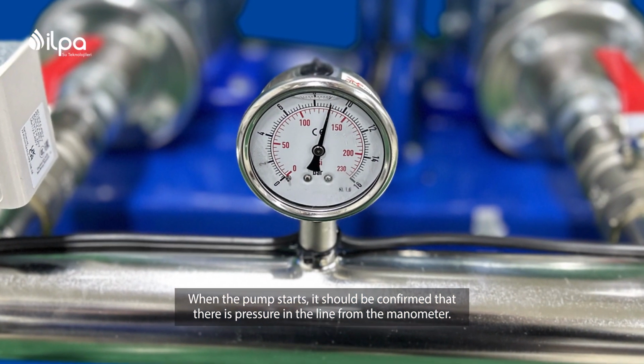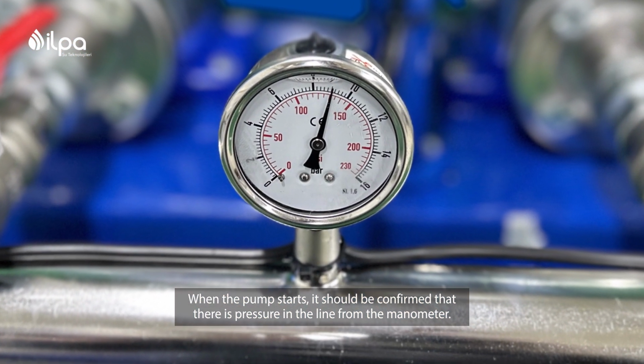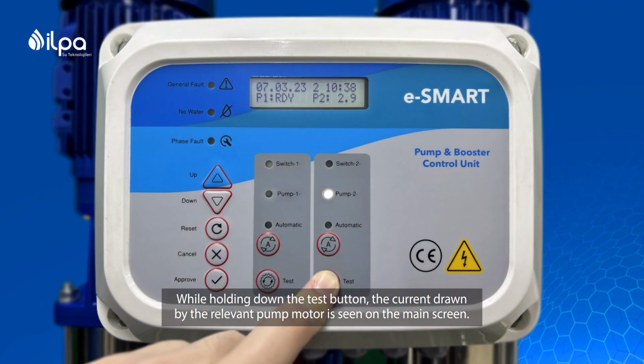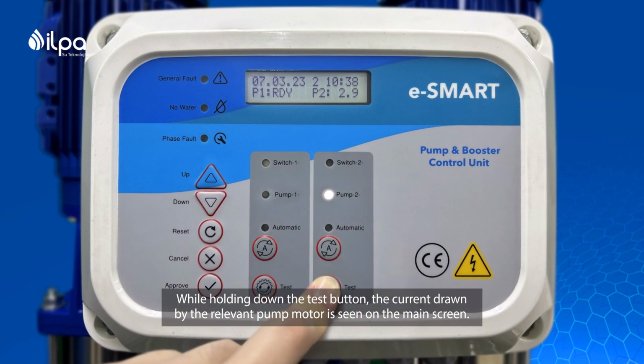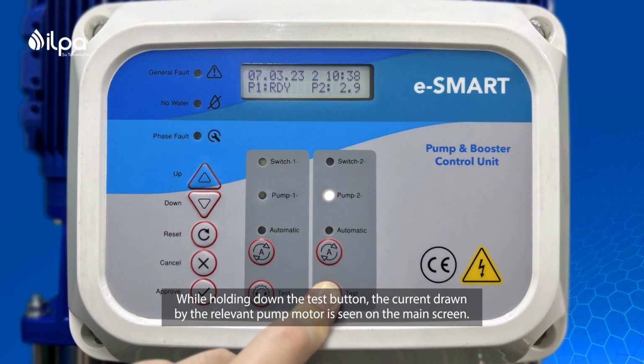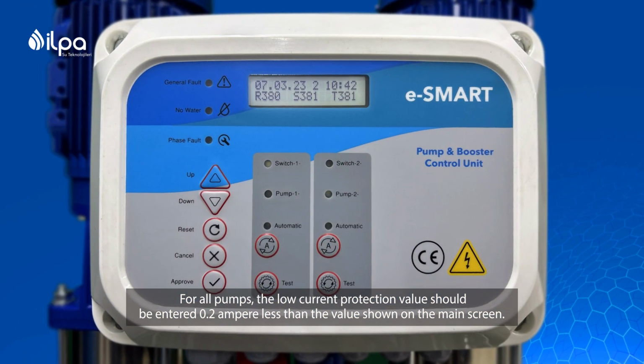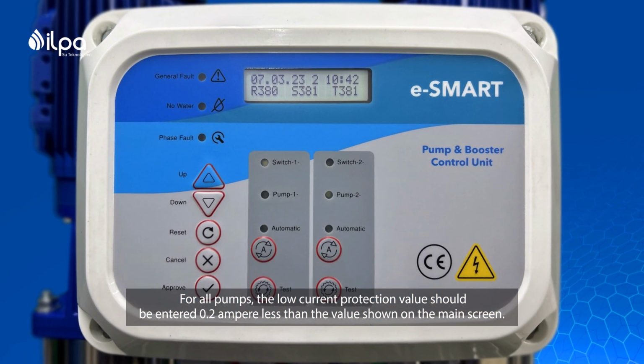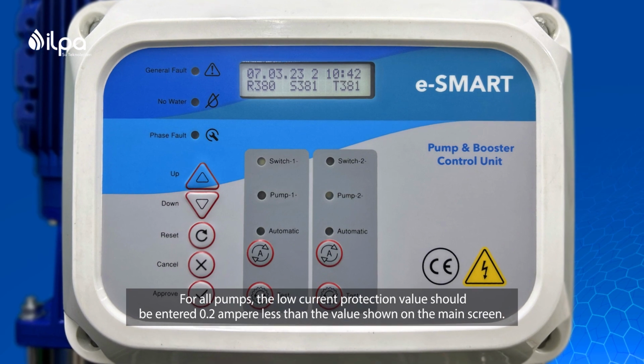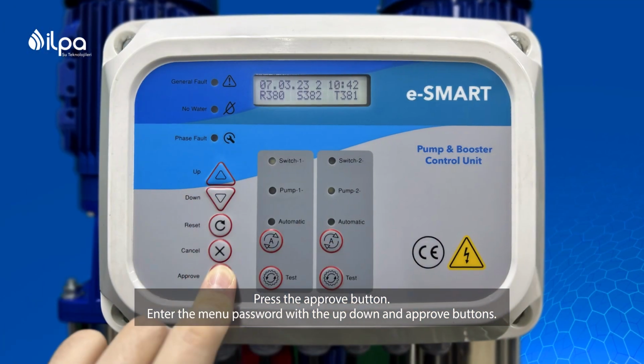When the pump starts, it should be confirmed from the manometer that there is pressure in the line. While holding down the test button, the current drawn by the relevant pump motor is seen on the main screen. For all pumps, the low current protection value should be entered 0.2 ampere less than the value shown on the main screen. Press the Approve button.